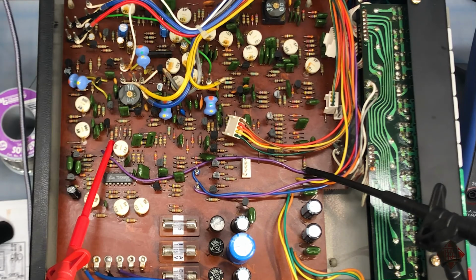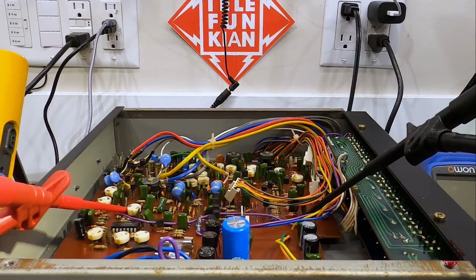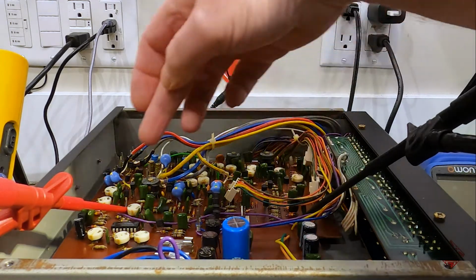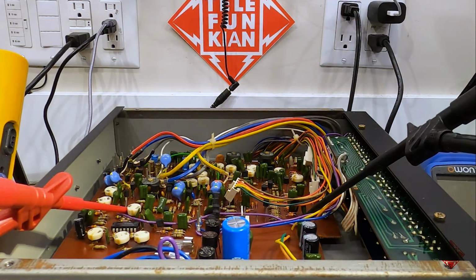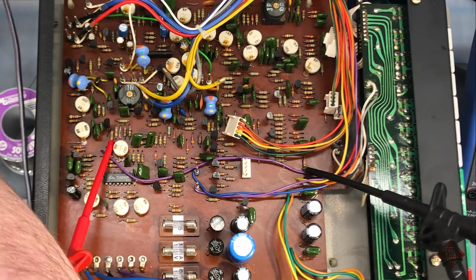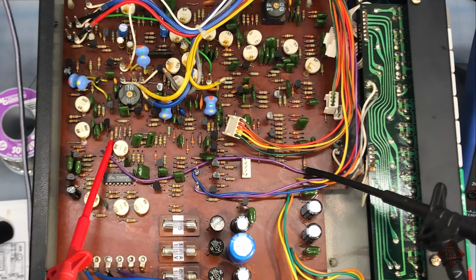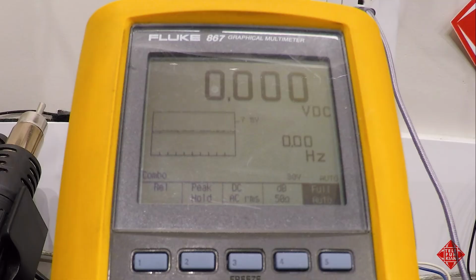So after recapping the power supply and putting in the new transformer, we want to check the power rails. Right now we're connected to ground and the positive 5-volt rail. I'll turn on the meter and turn on the variac, which is set at 120 volts AC, our local power here. Turning on the instrument, we have 5.057 volts DC on the positive 5-volt rail.